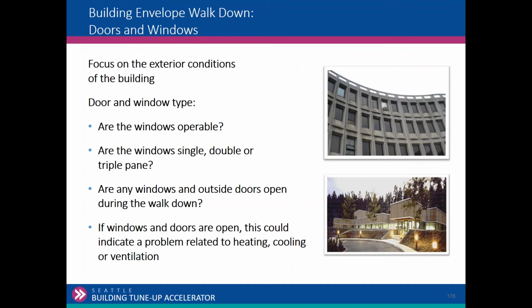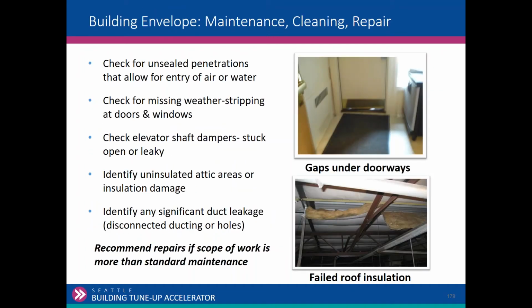Are there any windows or outside doors open during the walk down? If you see doors open, what's that a symptom of? If you saw doors open or windows open on a day like today, too hot somewhere or inadequate ventilation. So we're just looking for unsealed or missing weather stripping, just the real obvious stuff as you walk around the building. Elevator shaft dampers, essentially they're open, and we've got a chimney inside the building. A lot of stack effect, whatever that's called.